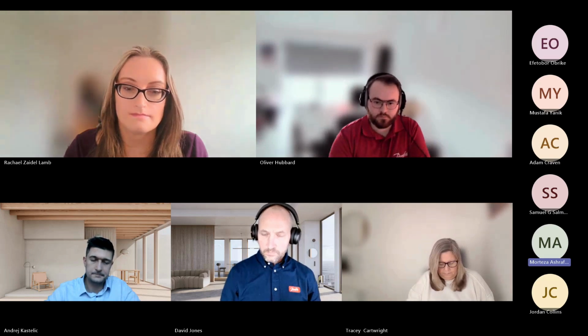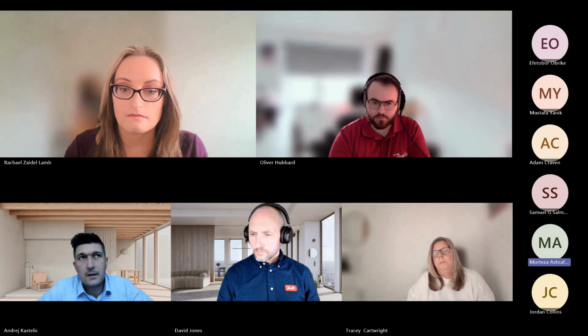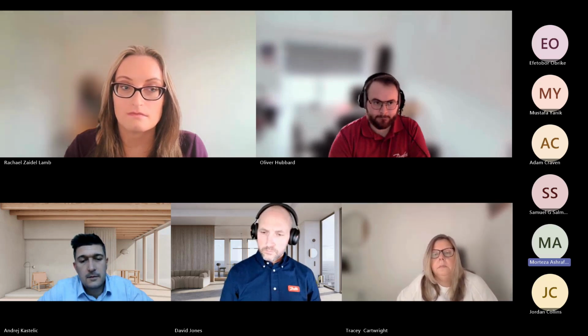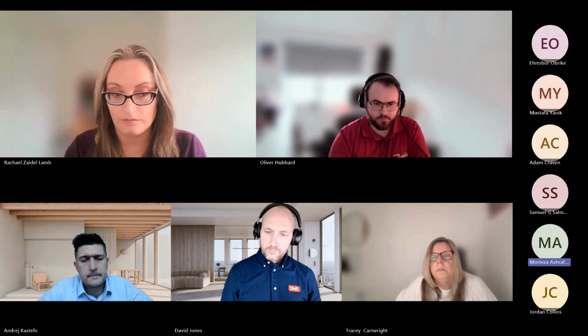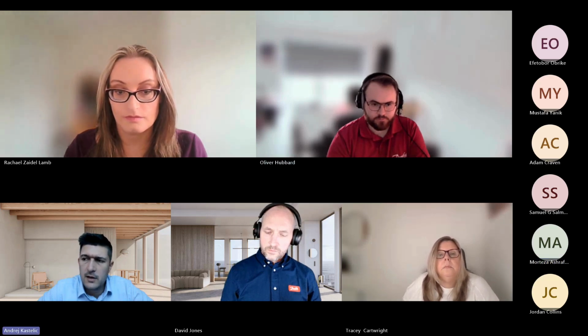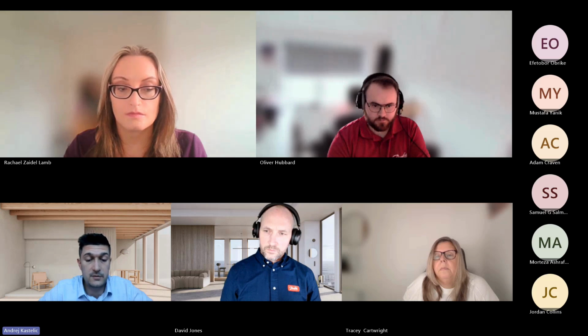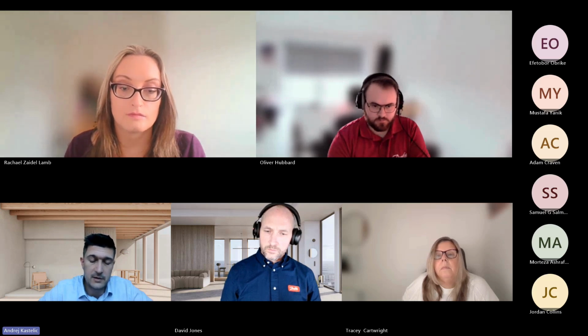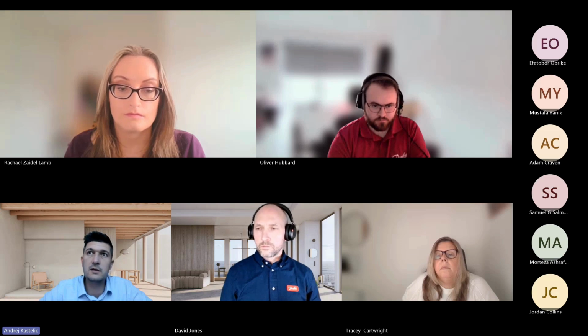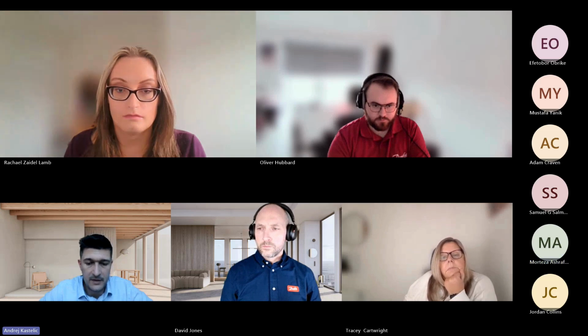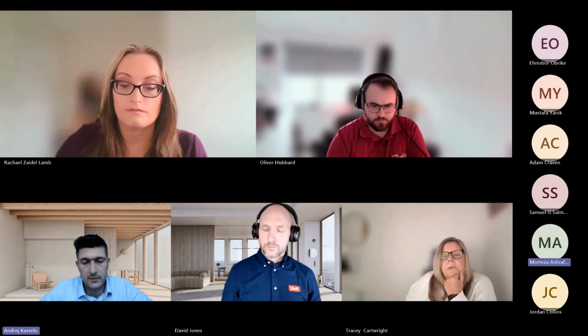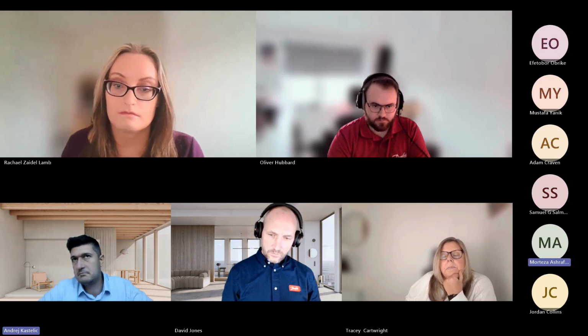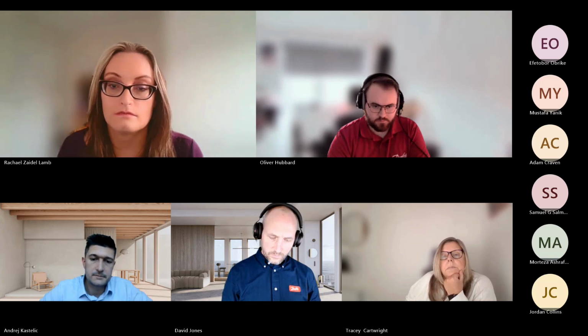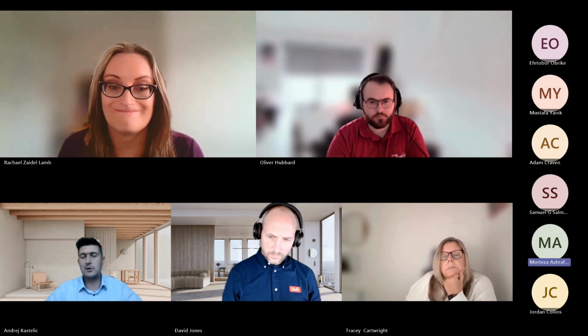Thank you so much. I just wonder whether we will be able to capture any notification or indication of scale building up within the valve from the data we receive. Very good question. We also tested different solutions available on the market, and what we have seen is that a valve filled with calcium carbonate has a reduced nominal flow. It cannot achieve the flow anymore. This could be quite substantial, up to 40–50% after, let's say, 100,000 cycles. Okay, thank you so much. You're welcome.